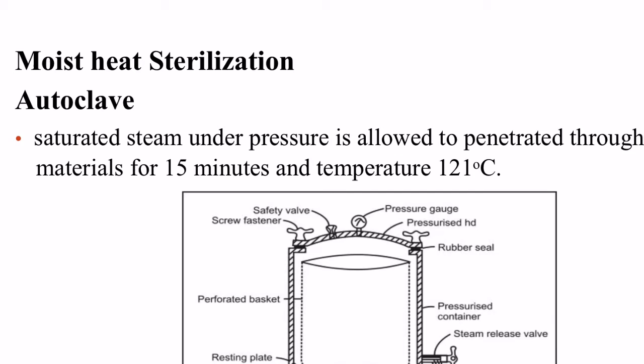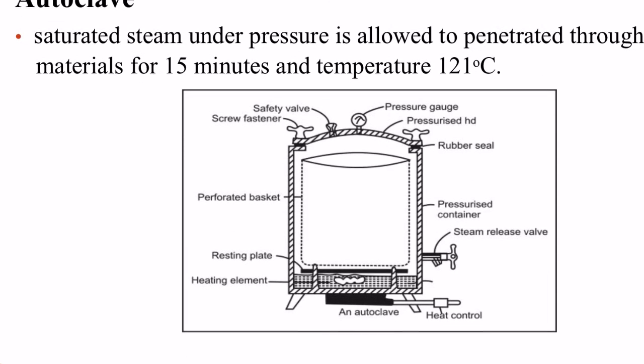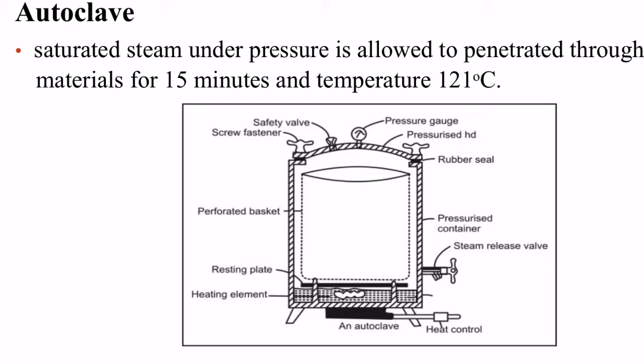Next is moist heat sterilization. In moist heat sterilization, we use water. In dry heat you use simple heat with no moisture or water involved, but here water is involved — vapors and steam are used. We know that the instrument is an autoclave, and in an autoclave we generate steam under pressure. The temperature is 121 degrees Celsius for 15 minutes at 15 lb pressure.